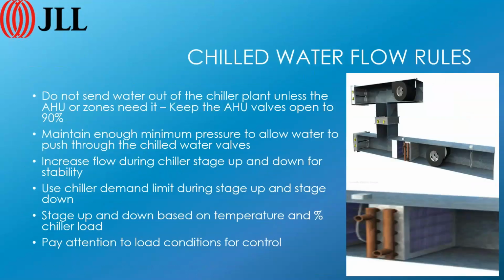So some chill water flow rules. We don't send water out of the chilled water plant unless the zones need it. So you don't pressurize the chill water loop and have a high delta P set point and hope that it's going to work out for you. You just don't do that. You maintain enough minimum pressure to allow water to push through the chill water valves, and that can be as low as, I've run systems down as low as 3 psi. The valves are mostly open. There's hardly any pressure drop across them, and 3 psi sometimes will work just fine. But typically you'll run it down to around 5 psi or so, and that'll work just fine.